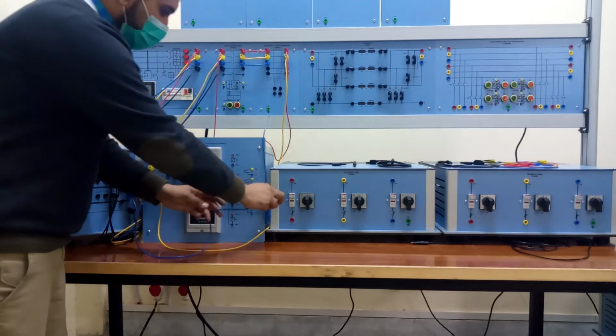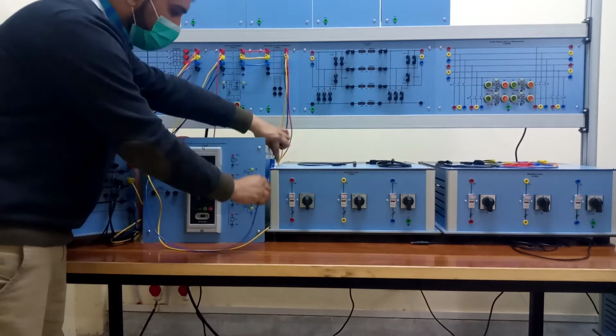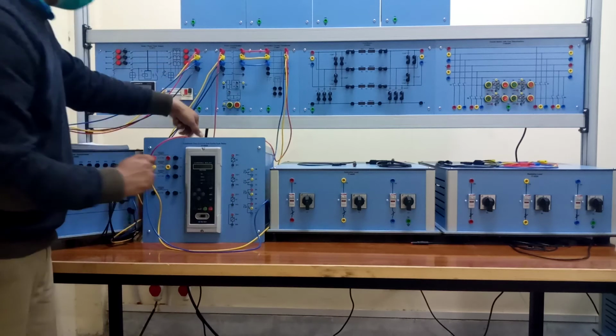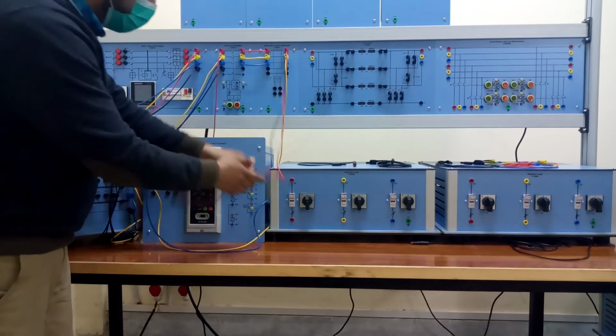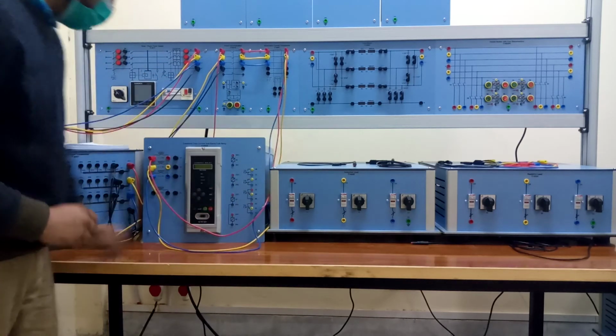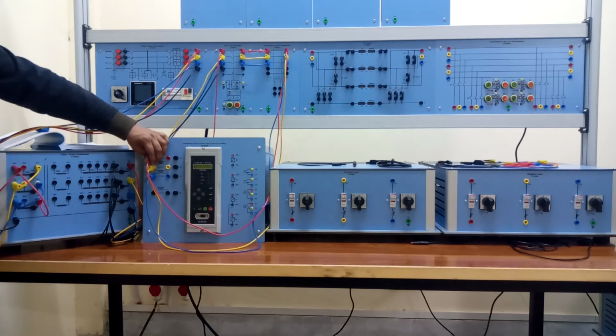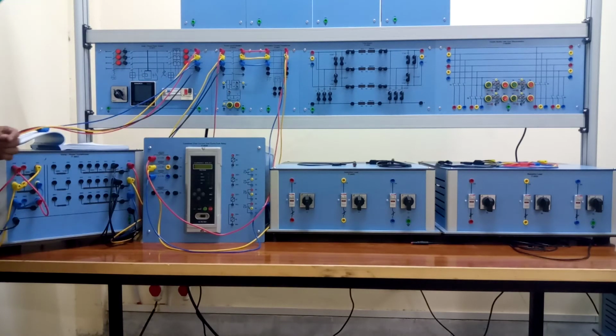So these are the connections. I'm going to hide these connections a bit so you can get a good view of what is going on here. These are connected to your summation transformer, so the current is now moving from this summation current transformer to your combined overcurrent and earth fault relay.